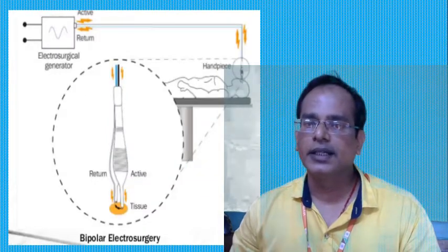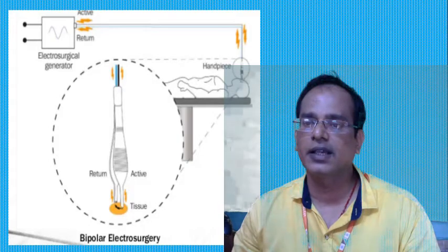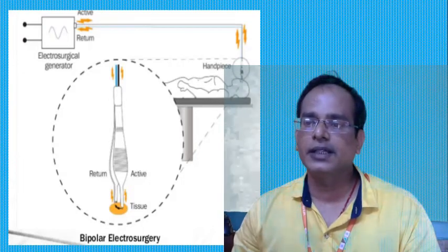Here, denaturation at temperatures above 45 degrees Celsius causes breakdown in the structure of living tissues and a disturbance of the function of protein molecules. Coagulation at a temperature of 60 to 70 degrees Celsius in the area around the active electrode leads to slow boiling of the intracellular fluid through the cell membrane. Here we also have another concept, the welding effect, that is initiated, which stops bleeding.